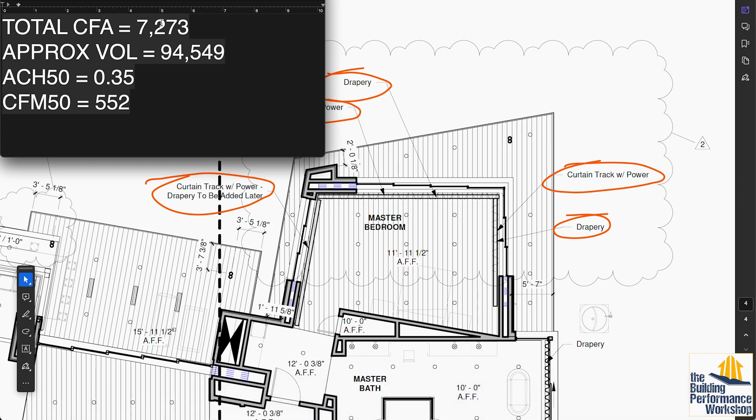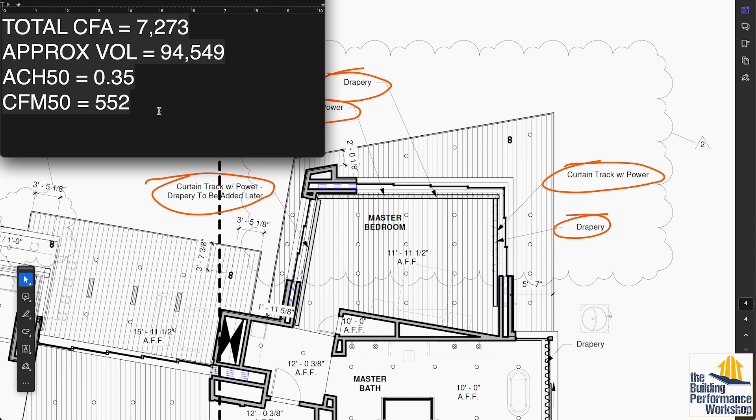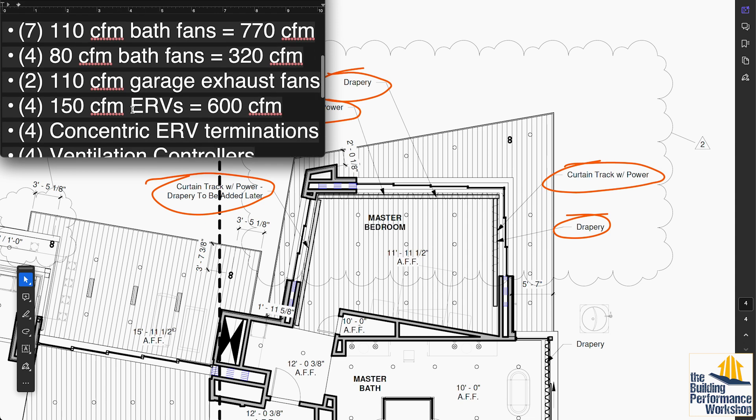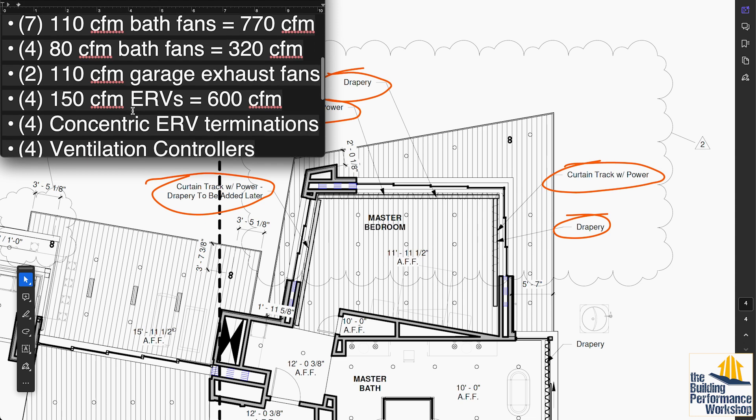We're going to move on to ventilation. Here's what I want to say about the air tightness. We have a total conditioned floor area of just the house and not the casita: 7,273. We've got mostly 12-foot ceiling heights, and we've got about a quarter of the house with 16-foot ceiling heights. So that's a total approximate volume of about 95,000 cubic feet. For a blower door test that would give you 0.35 ACH50, that's a CFM50 of the blower door reading itself of 552 CFM. That means that if we blow 552 CFM of air with any devices out of this house, we are doing the blower door test.